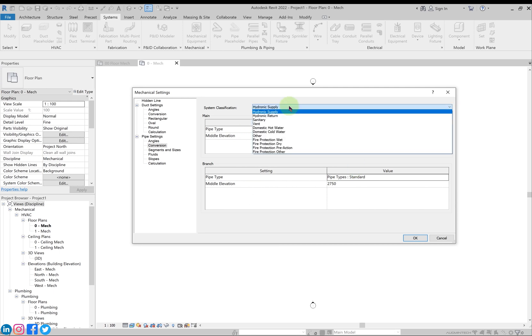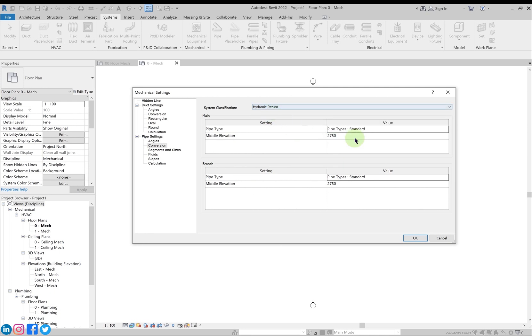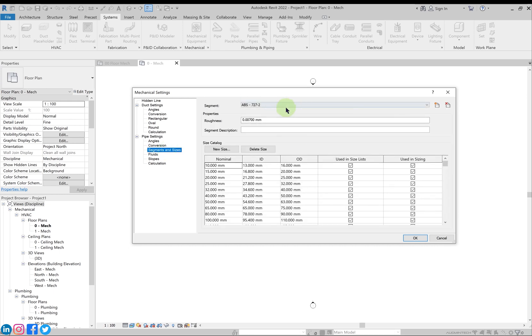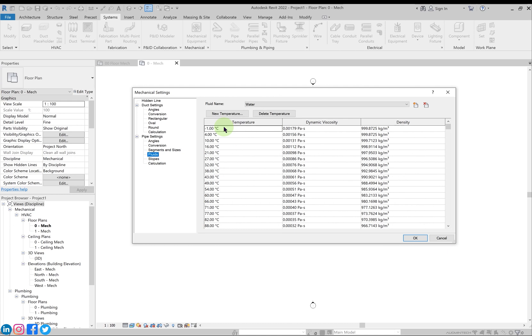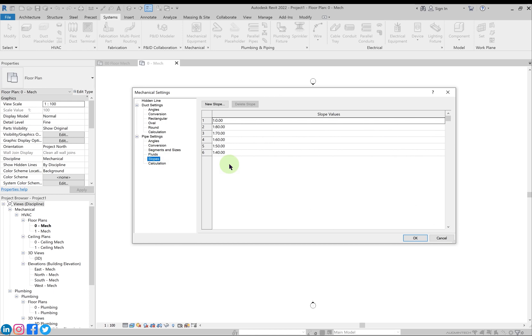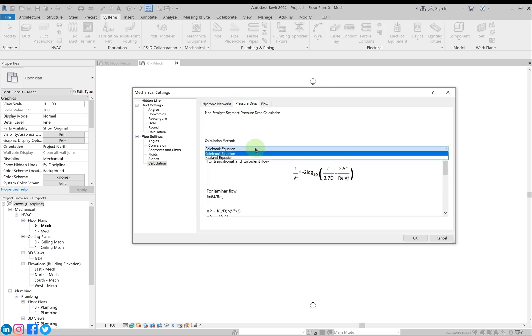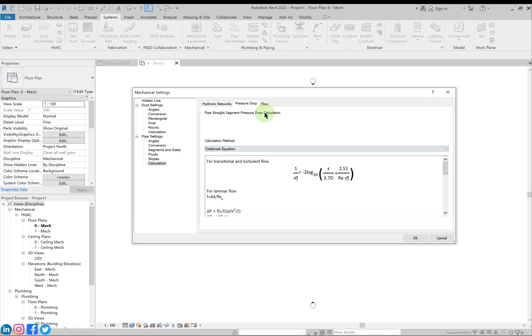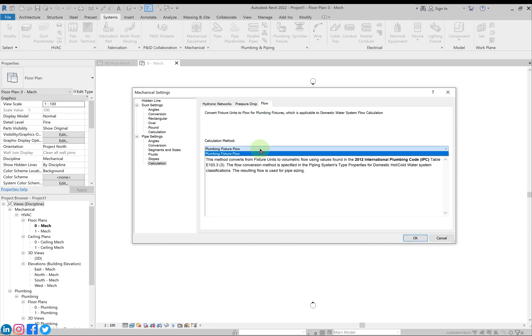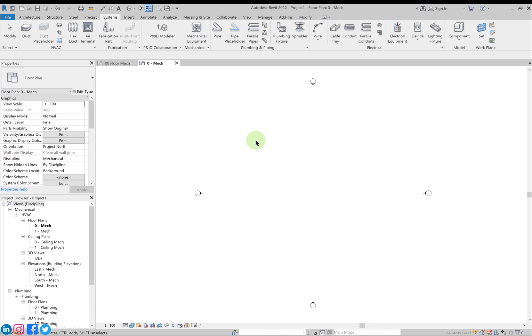If you want to alter any value for hydronic return, you get the options for hydronic return and can change any of these values. In segments and sizes, similar to ducts, fluids — what type of fluids, their temperature, viscosity and density — are defined. We also have slope values, and for hydronic networks, equations for pressure drop and flow calculation methods. Let's keep these to default settings and click OK.